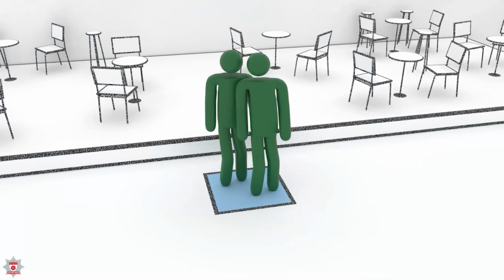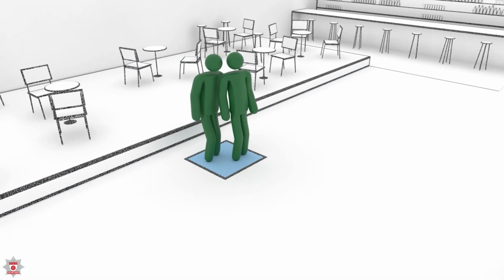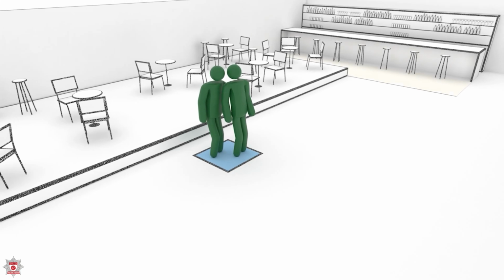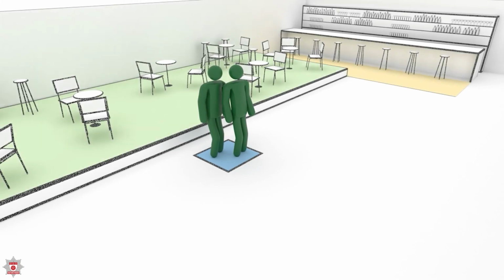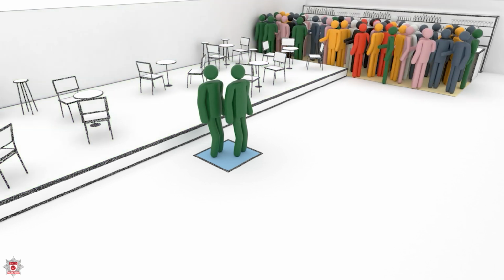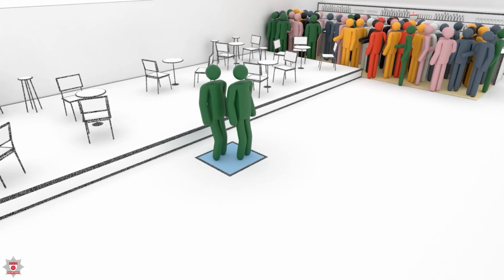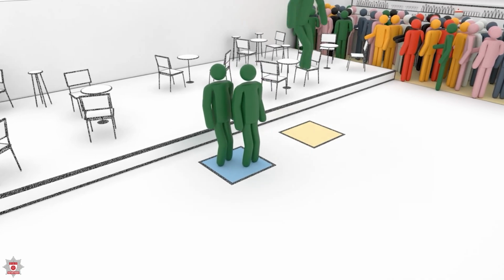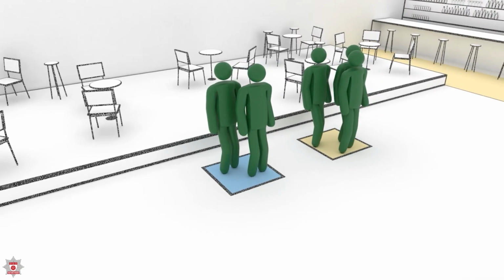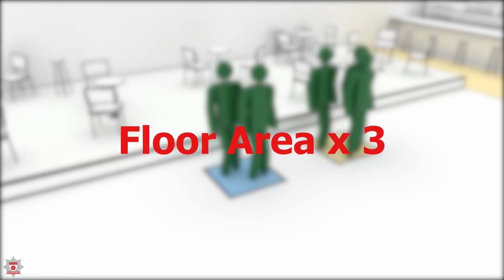The other areas of the building now also need to be calculated. As mentioned before, the bar area and the seating area are used differently to the main hall or dance area. At the bar, people are more tightly packed together than on the dance floor as they are waiting to be served. The bar area is a 2 metre space around the bar that the customers will be using. The number of people per square metre is increased to 3 people per square metre. So this calculation will be the floor area within the 2 metres around the bar multiplied by 3.